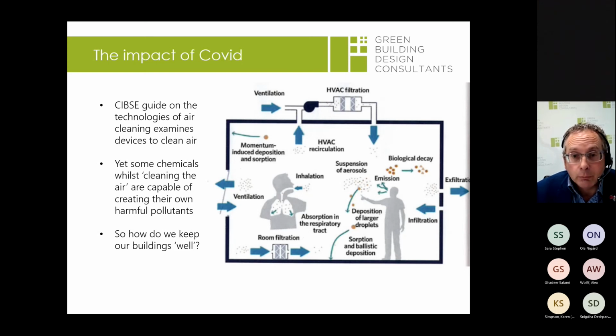We're also looking at bringing more fresh air in. With the risk that COVID-laden extract air, sucked at ceiling level, returns to the central plant, we must avoid mixing it, as is common practice to save energy, with incoming fresh air, which could bring COVID spores back down the supply duct in a circular motion. So at the moment, we're concentrating on full fresh air systems in the short term to avoid extract air bringing harmful pollutants back in, which again flies in the face of saving energy, where normally we'd look to bring in just the building regulations minimum fresh air.